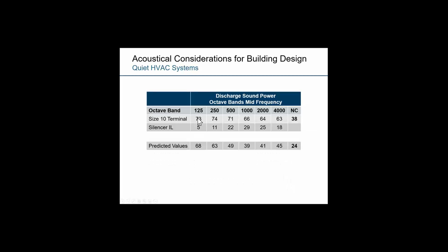Well, in general, when you have a terminal unit, there's typically discharge sound power associated with it. Depending on the airflow and the static pressure and the size of terminal, there'll be the corresponding sound power associated with it. From that sound power, we typically deduct the silencer's insertion loss. Like I mentioned earlier, this would be a straight deduction. And by doing that, you can see the formula here would effectively yield a predicted value of a very quiet discharge sound level, approximately NC24.